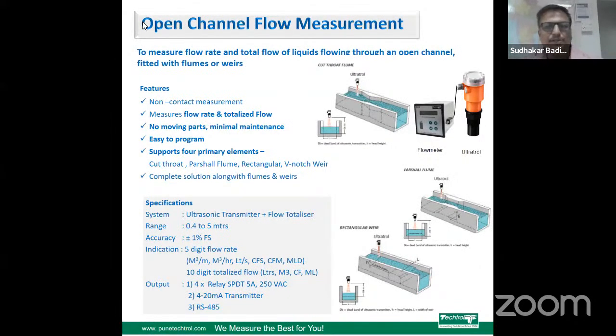So first is open channel flow measurements. Here we are generally giving ultrasonic level transmitters along with the flow computation device, that is a TOCF controller. So this is suitable for almost all types of weirs and primary elements like cutthroat flumes, Parshall flumes, rectangular weir, V-notch weir. And you can see the installation part.